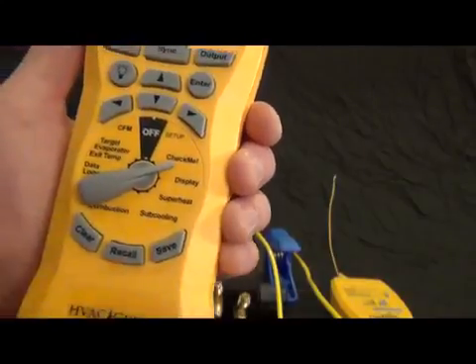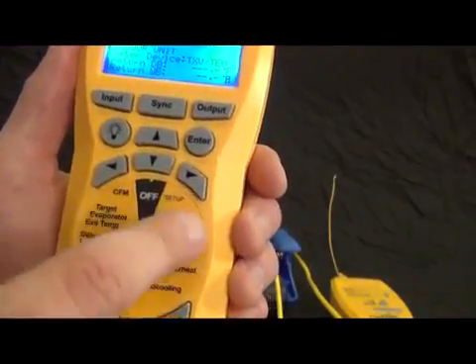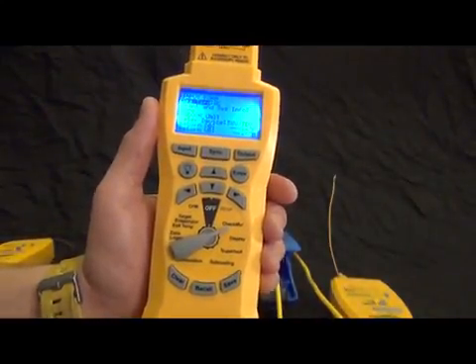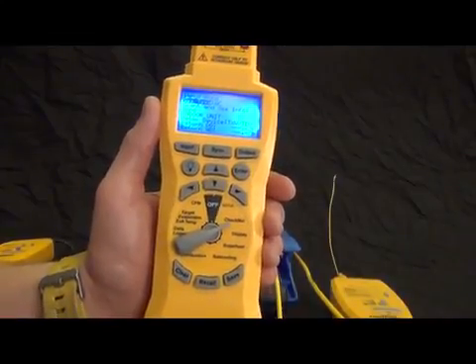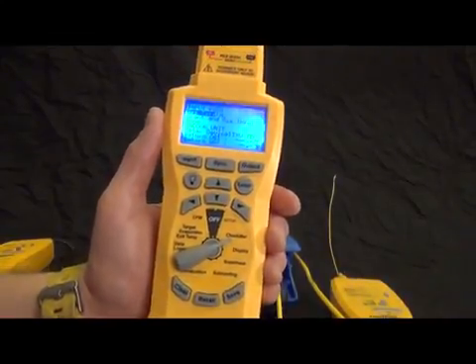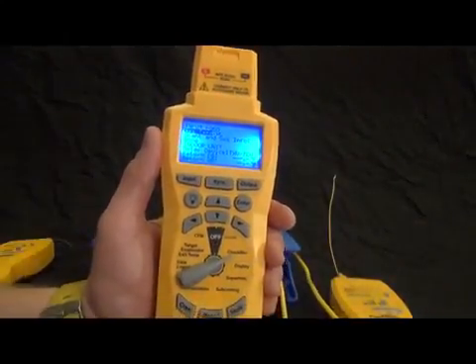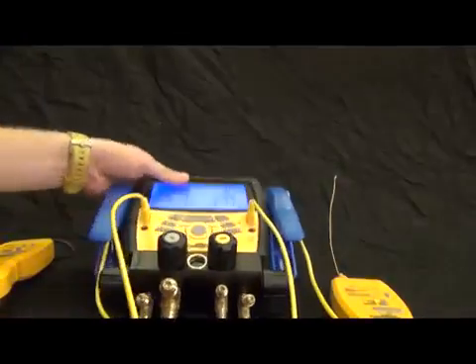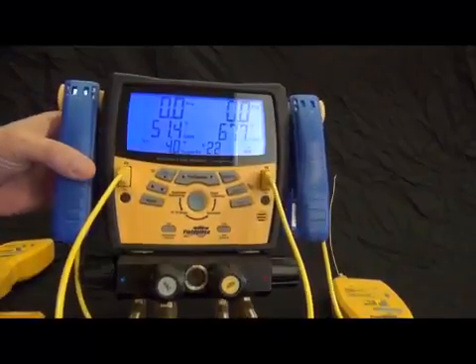check-me, superheat, subcooling, any pertinent of the tests. But I'm going to do the check-me test. Check-me basically combines delta T, superheat and subcooling into one test. It completely looks at the entire system and all the measurements involved. It takes about 10 pieces of data and calculates and diagnoses a system based on those 10 pieces of data. So what the S-Man 4 is responsible for is for six of those pieces of data.